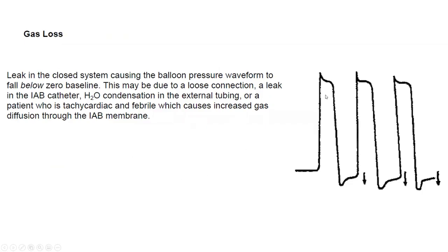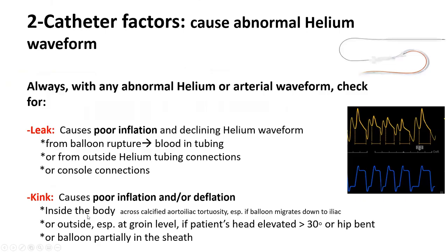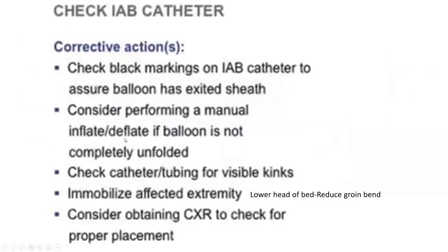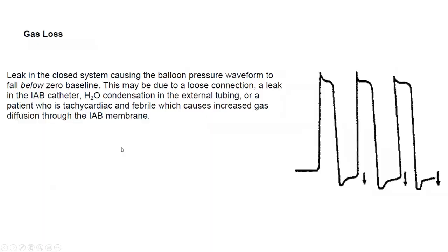Now, this is a waveform of a poor balloon inflation, which typically you'll see that inflation get less and less with every cardiac cycle. Typically, it's due to a leak, but like I said, it can also be due to a kink. So you verify all the things we talked about.